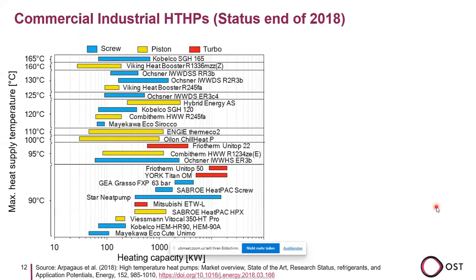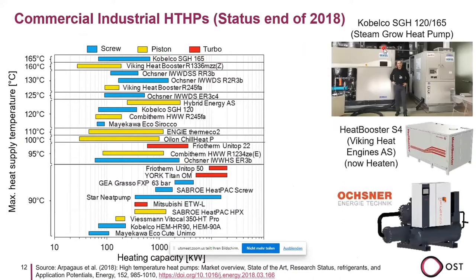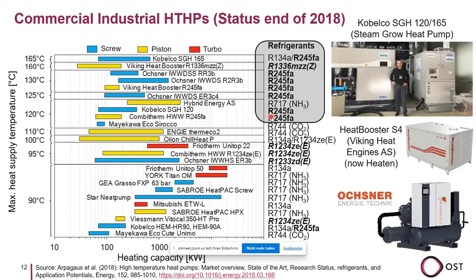This is a graph that we showed also last time. It's the status of end of 2018. So just several heat pump products as a function of the heat supply temperature and heating capacity. Here on the top, we have Kobelco, the Japanese, then Viking Heat Booster, then are now called Heaten, and Ochsner. So don't go into detail, but important point is the refrigerants which are used.